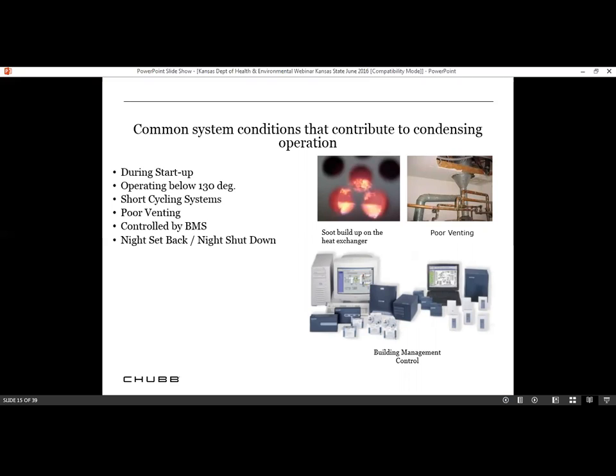Controlled by boiler management systems, night setback or night shutdown, where the setback might be if you've got a high pressure boiler and you have an operator. A lot of jurisdictions do this, and licensed operator, they will decrease the pressure at night to 15 and below, so they don't have to have a full-time operator. That may suit the operation, but it doesn't do any good for the boiler. Or they shut it down, and the next morning you got to come in and start the system back up.